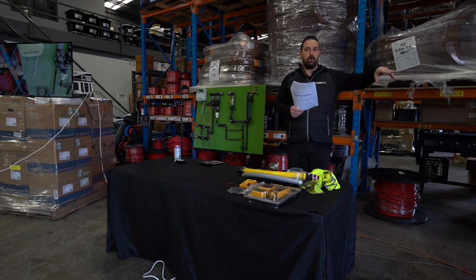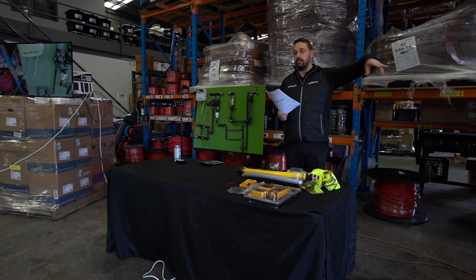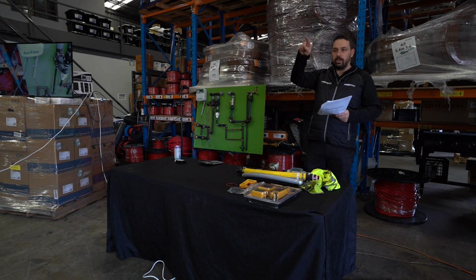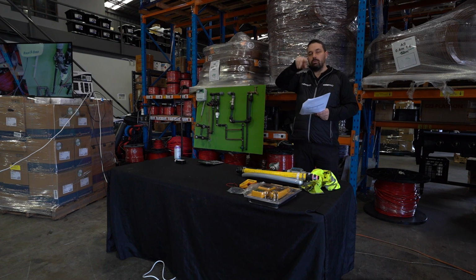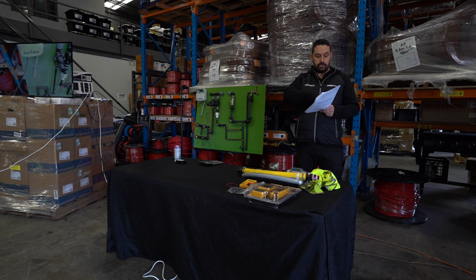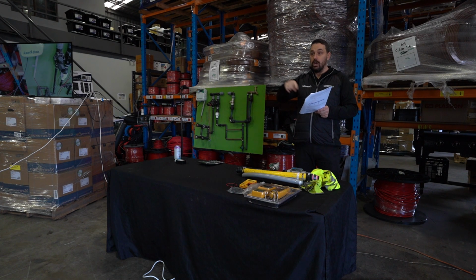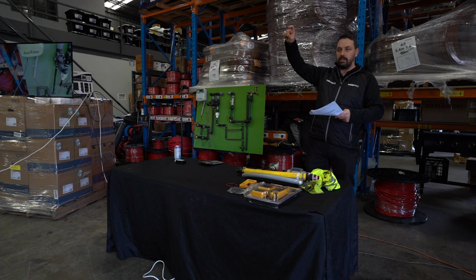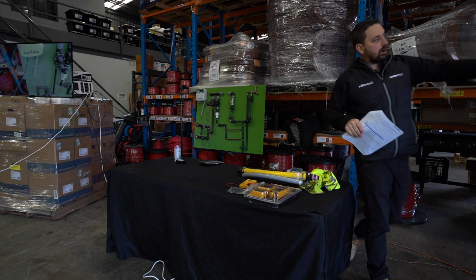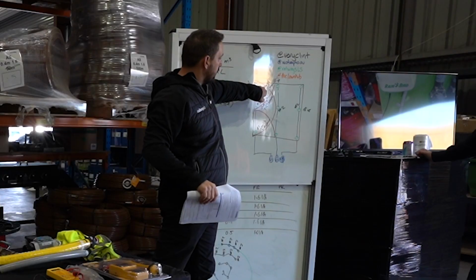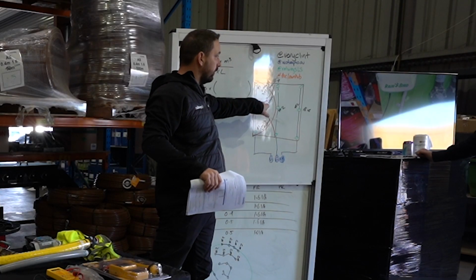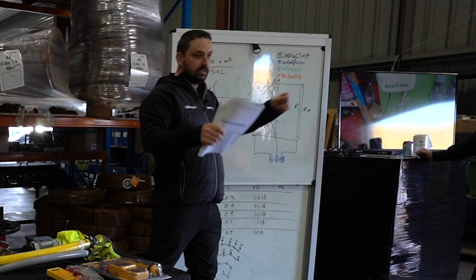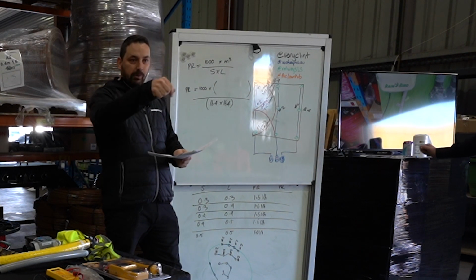A lot of the time, when we're doing this, you'll see on our designs, and not just our designs, anyone's designs, a hashtag number. In a design, you would see Rainbird 3500 series sprinkler with a number 2 nozzle unless noted, because that's our predominant default nozzle. And then you would see on the drawing, like Clint's got here, hashtag 1, and we wouldn't necessarily put a hashtag 2 on that because that's the default of the legend. Anywhere that is different to the standard, we would make a point of that.